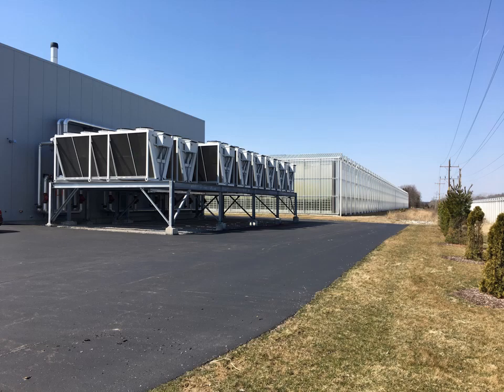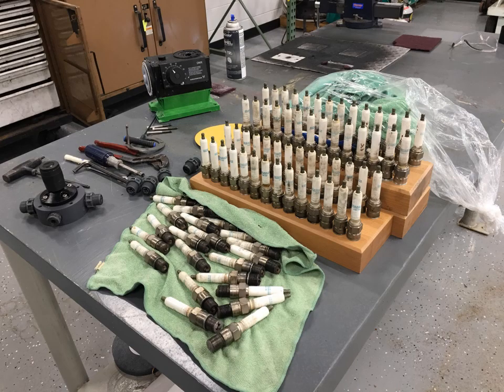This 24-cylinder engine has 24 spark plugs, so there is some maintenance involved — oil filters, spark plug changeouts, and after a number of years there'll be a head rebuild. All of that can be built into a service and maintenance contract. Maintenance costs factor into your economic pro forma, and it's often around one to one-and-a-half cents per kilowatt-hour equivalent value, somewhere in that range.